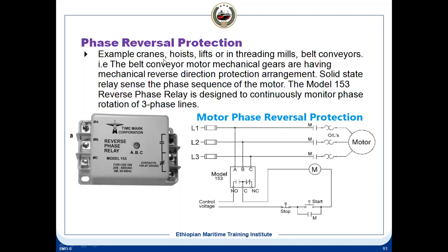Examples are cranes, hoists, lifts, and belt conveyors. The belt conveyor motor's mechanical gears have a mechanical reverse direction protection arrangement. This is a solid state relay. It will sense the phase sequence of the motor, and whenever the phase sequence changes, it will trip. So this is called phase reversal protection.